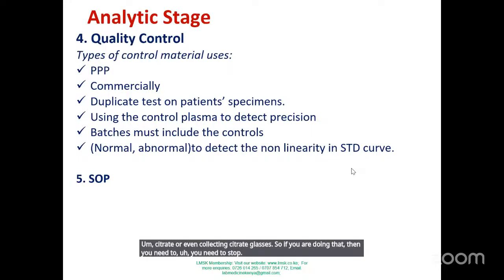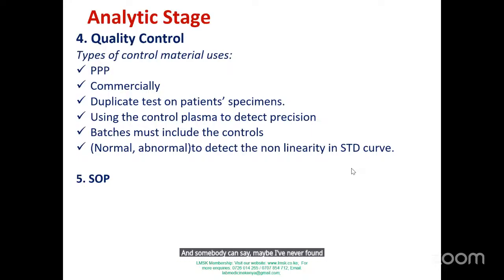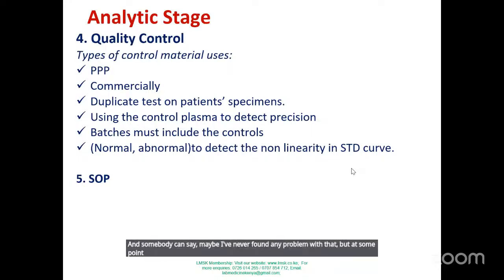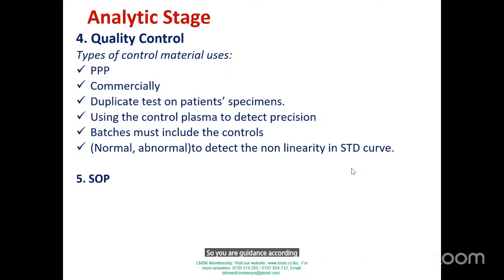And somebody can say, maybe I've never found any problem with that, but at some point you could have given a wrong result without knowing. So it's always good to follow the procedure. Again, look at your inserts and store your reagents according to the manufacturer's prescribed insert. If it is manual, follow the instructions that have been given.